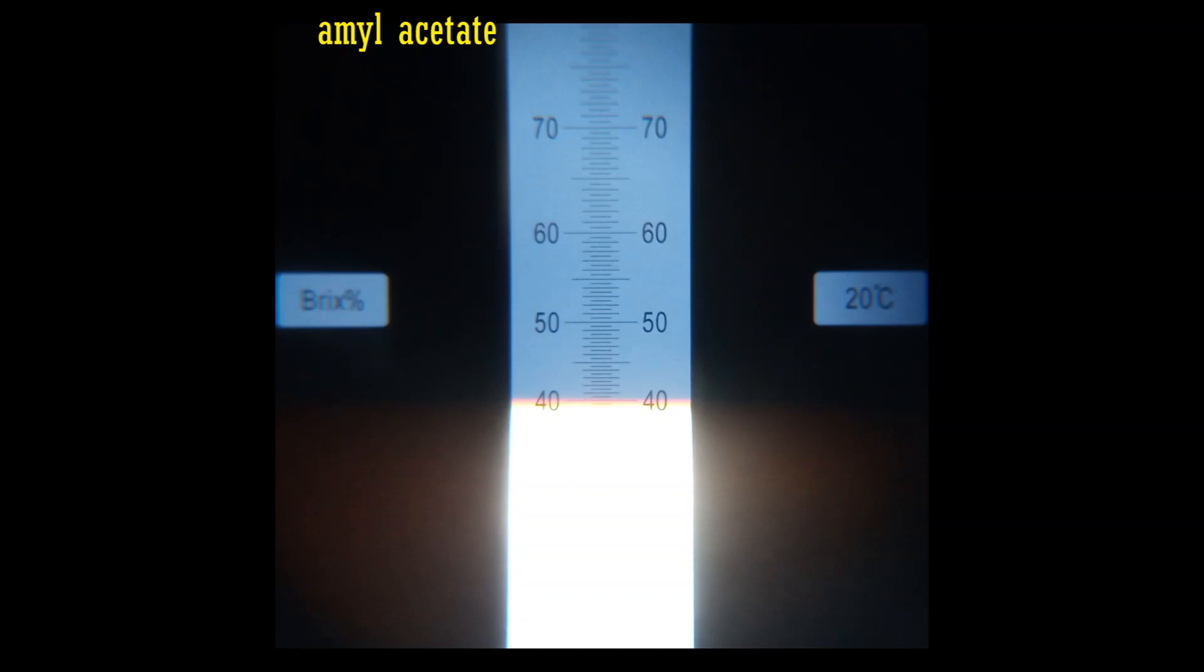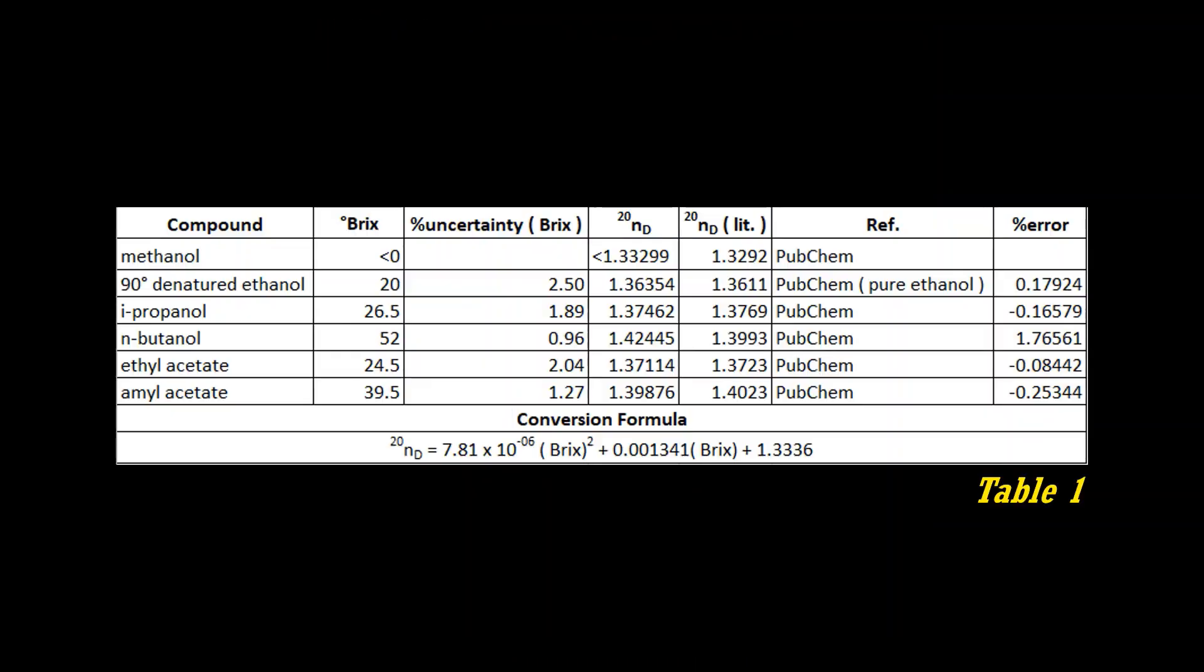Final results are summarized in Table 1. The resolution of our refractometer is 0.5 BRIX. From that, uncertainty percentage of each measurement is calculated. BRIX grades are converted into sodium D-line refractive index using formula displayed and compared with reference.